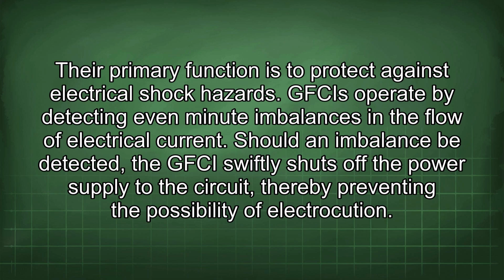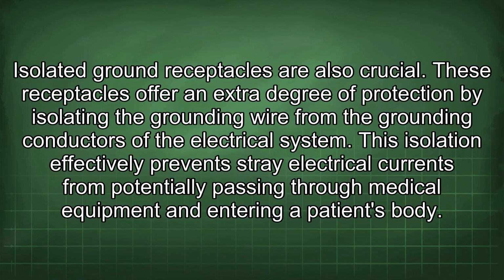of electrocution. Isolated ground receptacles are also crucial. These receptacles offer an extra degree of protection by isolating the grounding wire from the grounding conductors of the electrical system. This isolation effectively prevents stray electrical currents from potentially passing through medical equipment and entering a patient's body.